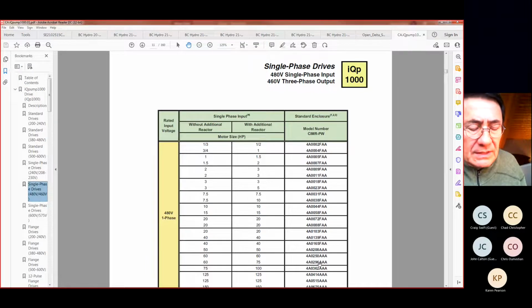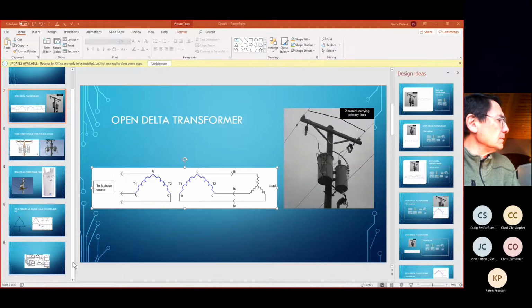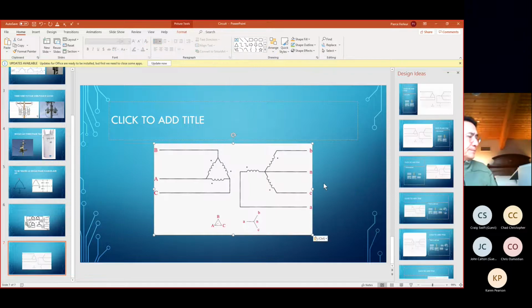we want to see as delta primary, Y secondary, with the center tap on the secondary grounded. And I will put that up right now. Bear with me one second. This is what we want to see. We want to see 3 lines coming into the primary on the power pole transformer, and we want to see 4 lines going out. This ground is critical.